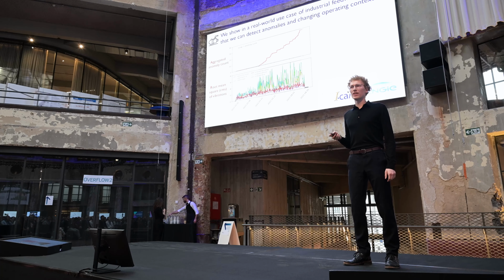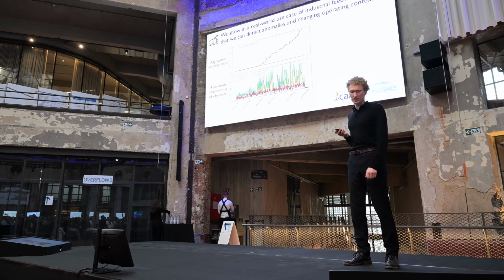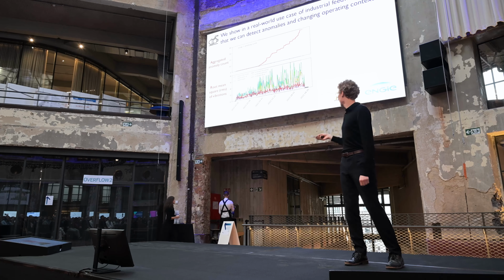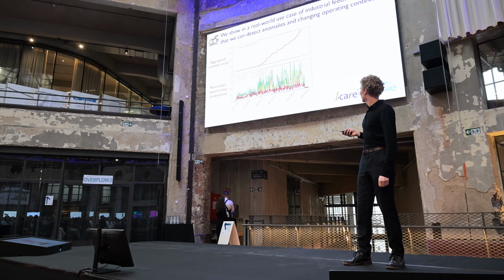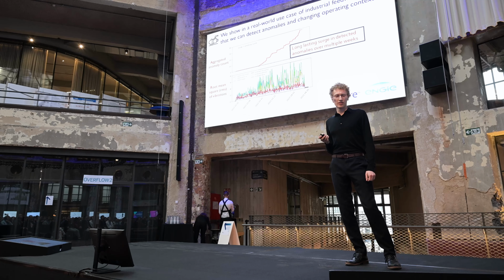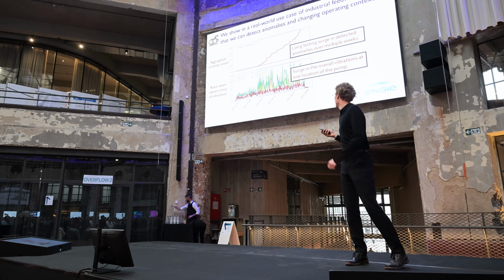Thanks to our industrial partners, we were able to show in a real-world industrial use case of industrial feedwater pumps that we can detect anomalies in that use case and changing operating context. In the given example, we have detected a prolonged period of anomalies over multiple weeks, and we could link this to increased vibrations at one specific location within the feedwater pump. But we had also many other examples.